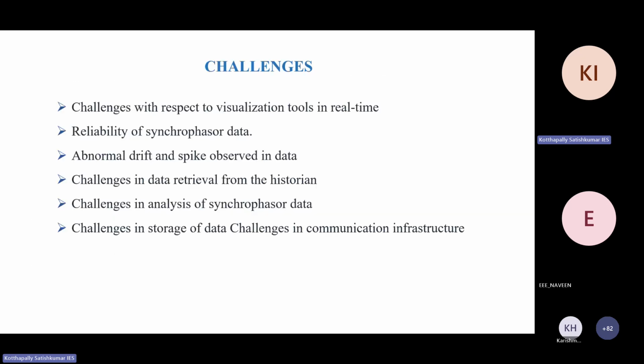So what are the challenges? As I told earlier, we have huge data, so you need some tools. That tool should take the critical substation, or wherever the fault comes, automatically select that substation, and display should be given for that particular substation, because you have 1400 PMUs. It is not practically possible to see 1400 PMUs' data at the same time. So you need to select using these analytic tools only; then you can see the exact data.